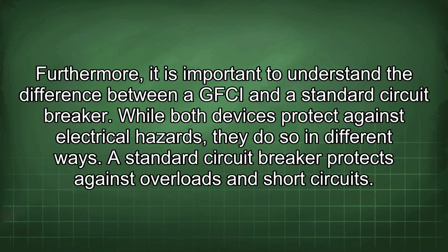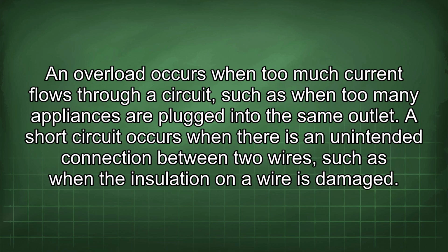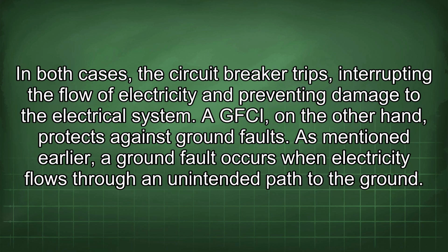Furthermore, it is important to understand the difference between a GFCI and a standard circuit breaker. While both devices protect against electrical hazards, they do so in different ways. A standard circuit breaker protects against overloads and short circuits. An overload occurs when too much current flows through a circuit, such as when too many appliances are plugged into the same outlet. A short circuit occurs when there is an unintended connection between two wires, such as when the insulation on a wire is damaged. In both cases, the circuit breaker trips, interrupting the flow of electricity and preventing damage to the electrical system.